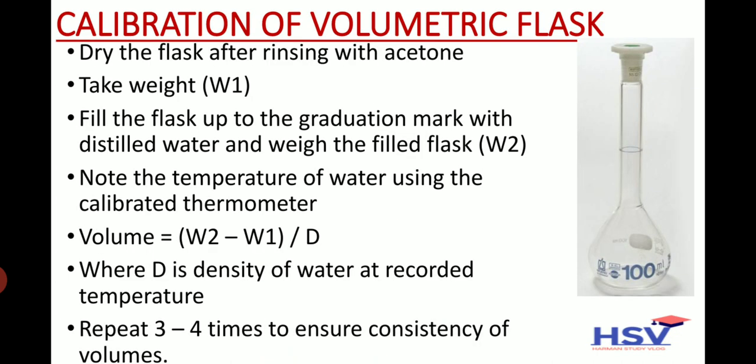Calibration of volumetric flask: A volumetric flask has a long-necked flask with a flat bottom at the base. Dry the flask after rinsing with acetone. Take the weight as Weight 1. Fill the flask up to the graduation mark with distilled water and weigh the filled flask as Weight 2.